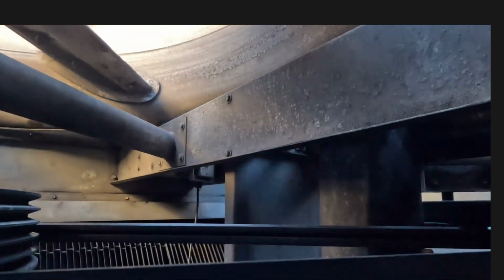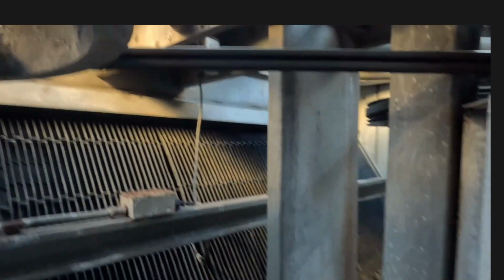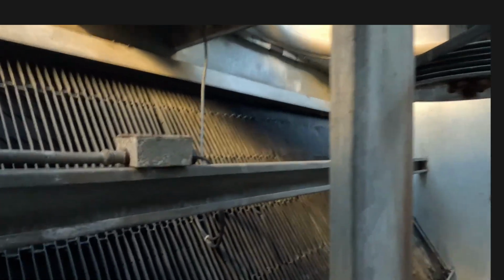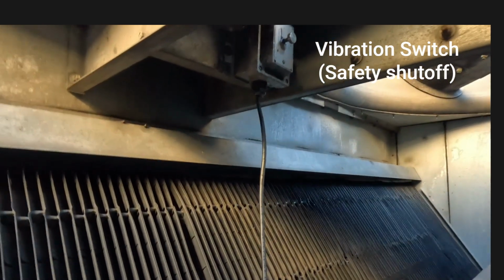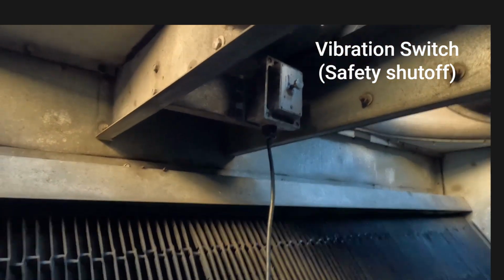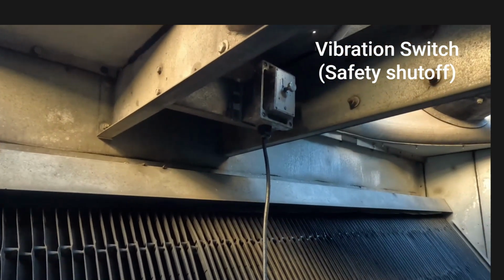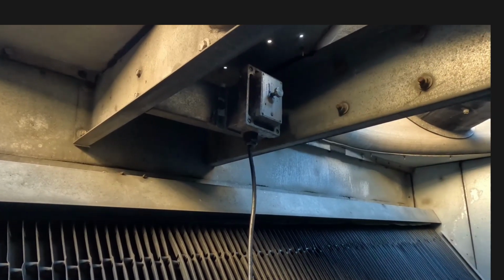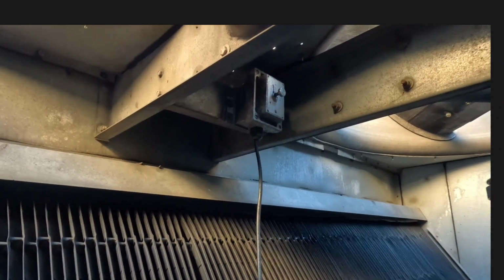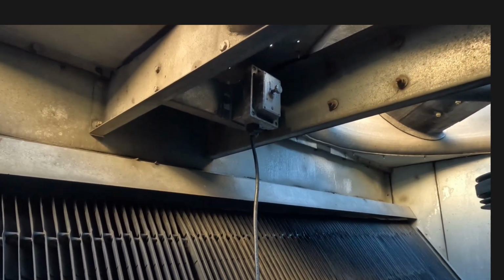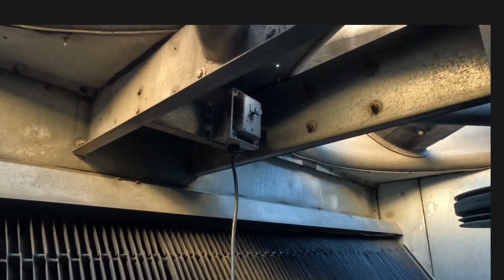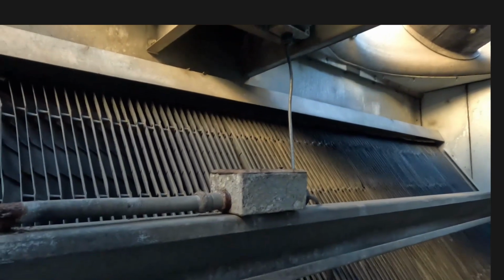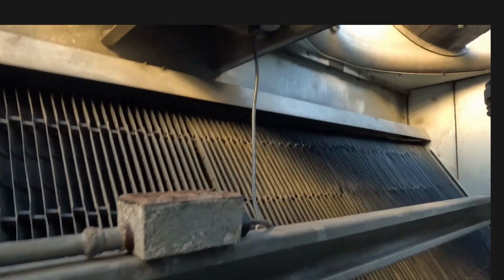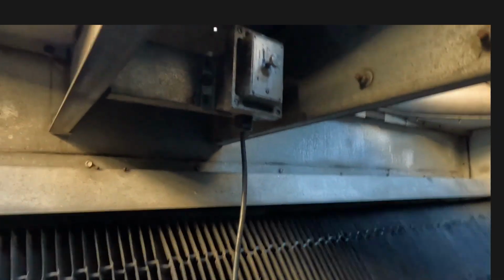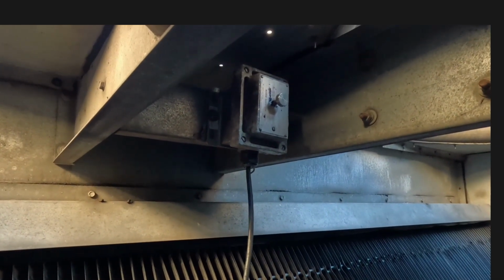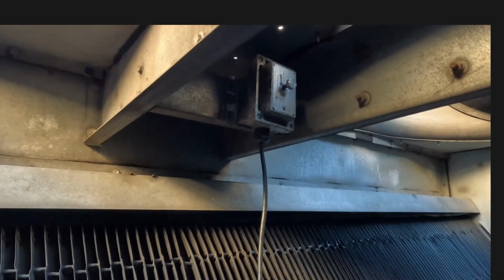Plus, what you do on a cooling tower maintenance. And there's the vibration switch. So that switch right there will detect any crazy vibration and stop the cooling tower from spinning so it can protect itself from catastrophic failure. So you'll often see these for cooling towers, vibration switch, and it has a manual reset button there.